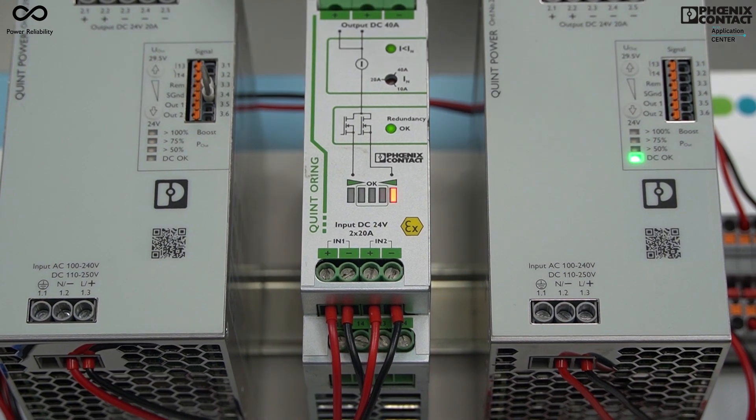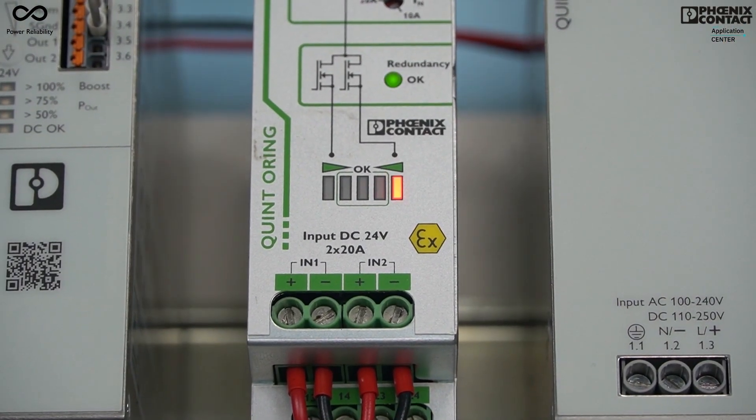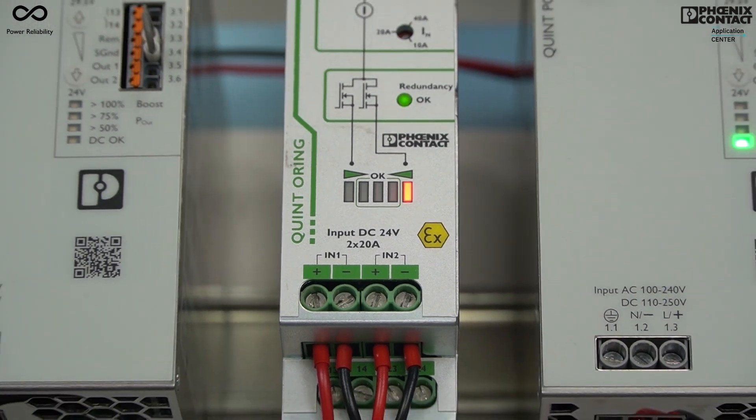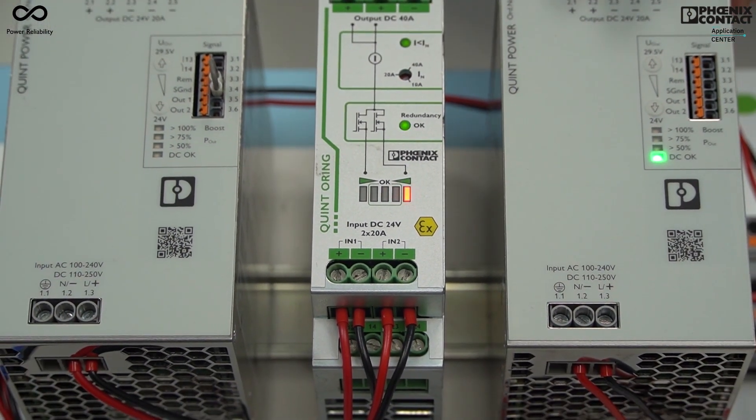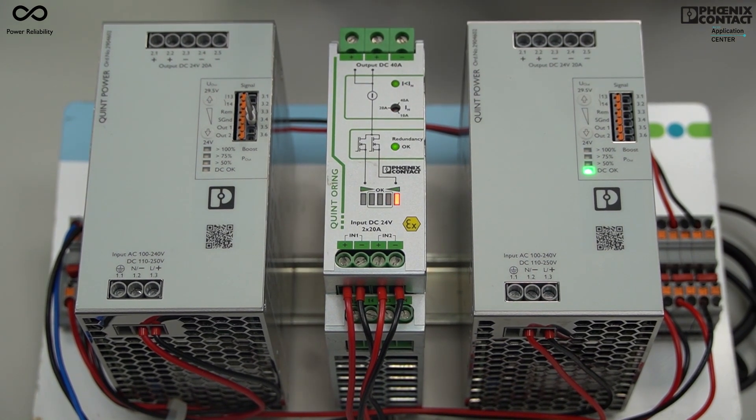Here you can see that the MOSFET is giving the alarm indication with visual as well as remote signals, and the healthy power supply is taking care of all the load. Your load is continuously working without any disturbance.